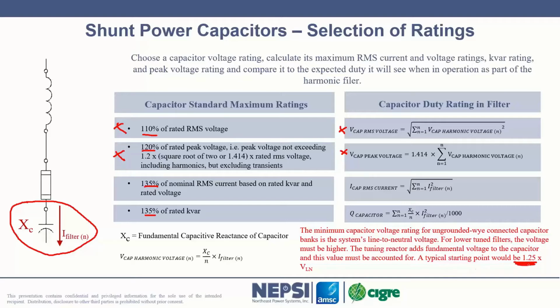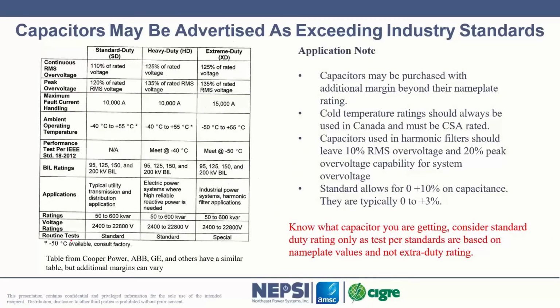We kind of have a starting point here: 1.25 times the fundamental is a good starting point. So if I have my normal line to neutral voltage here, I would typically at least start at a value of about 1.25 times that value to come up with my value of X of C. It's a starting point. It's not always going to be correct. It depends on how much current you have flowing into your filter.